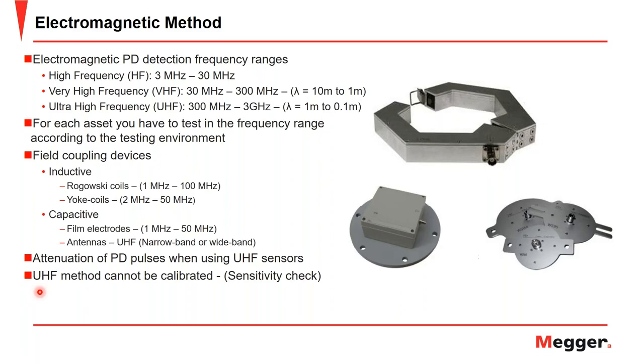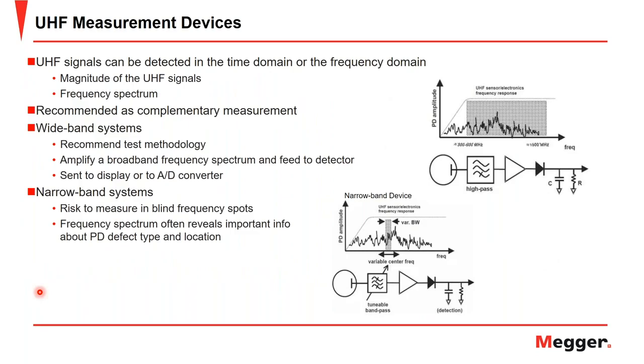Instead, they have what is called a sensitivity check, and we will cover that in detail in the next couple slides. So here we have an example of two different types of UHF measurement devices. And the UHF signals can be detected in either the time domain or the frequency domain. The time domain can be characterized by the magnitude of the UHF pulse, where the frequency domain result is a spectra which shows the amplitudes of various frequency resonances stimulated by the PD pulses themselves.